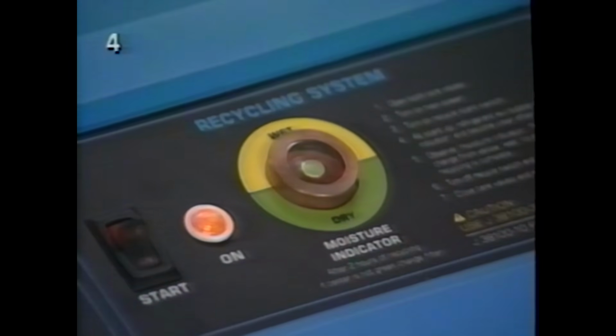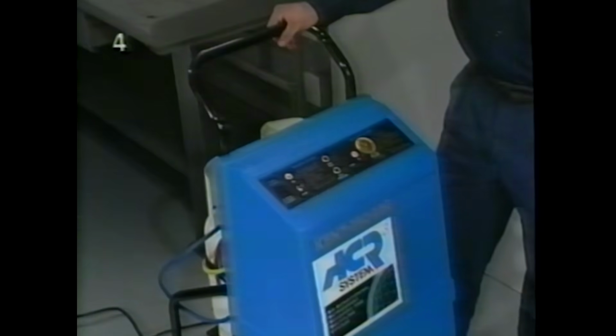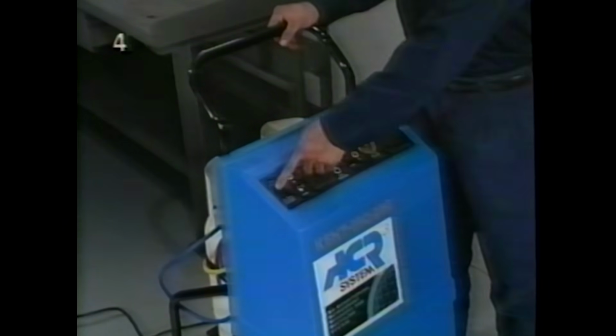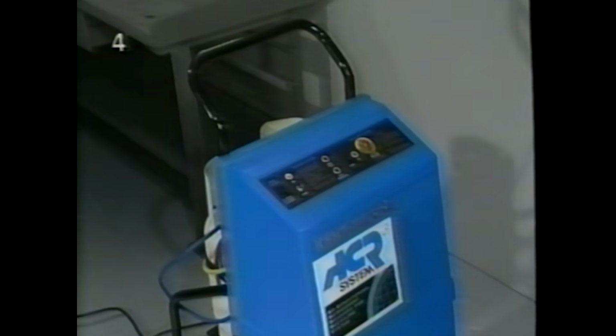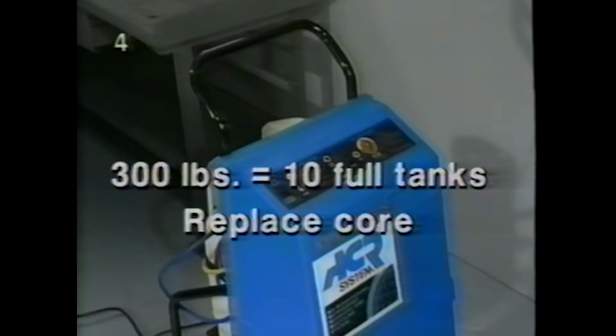Let the ACR3 go for at least half an hour until the center dot in the moisture indicator turns the same shade of green as on the reference sticker. It could take up to 2 hours if the moisture indicator is yellow at the start. Turn the recycling station off when the dot turns a proper shade of green. You can use recycled refrigerant to recharge AC systems in exactly the same way as new drums. After recycling about 300 pounds of refrigerant, that's about 10 full storage tanks, the filter dryer core should be replaced. You'll know it's time when it takes more than 2 hours to recycle a full storage can of refrigerant.